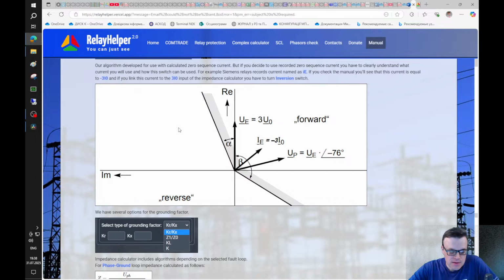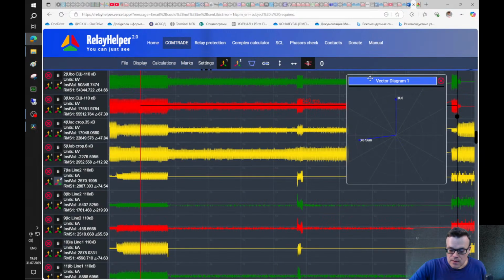Here, this is a picture from a Siemens manual, and here you can see the current that is usually named IEE in Siemens relays. It equals minus 3 times the zero sequence current. So if we rotate this vector phasor by 180 degrees, we should see the same picture.